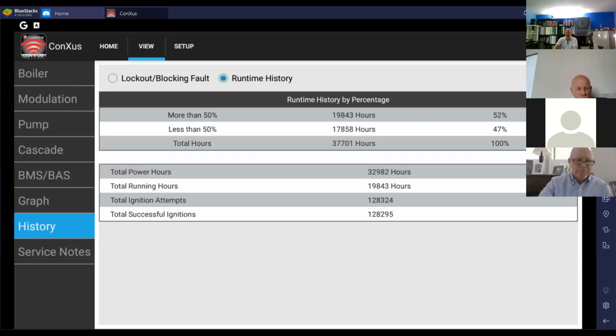And if we wanted to improve it, this might be where we would do it. And it's letting you know that it spends about half of its time above 50% firing rate and half of its time below 50% firing rate.